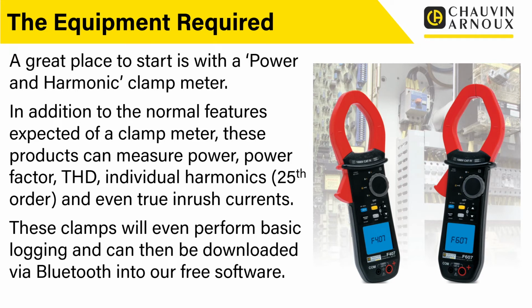They're generally not the sort of thing you'd use for logging or power quality analysis, but they are a great starting point tool or fault finding tool. If you're starting to trace an issue and chase into it, is it that phase? Is it that phase? Is it that circuit? What have I got on there? They're a really quick, easy, handy solution for doing these sort of things. And if you're going to buy a clamp meter anyway, really, you want to be looking at a power or harmonic clamp meter. They also do DC as well, so they're AC/DC, which is really good. You've got an AC clamp, DC clamp.